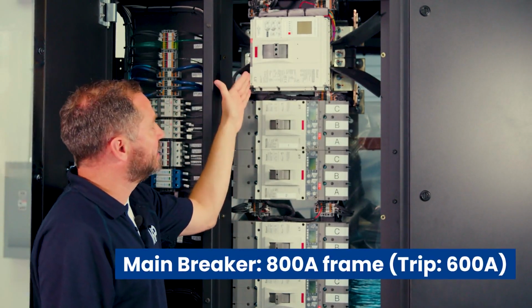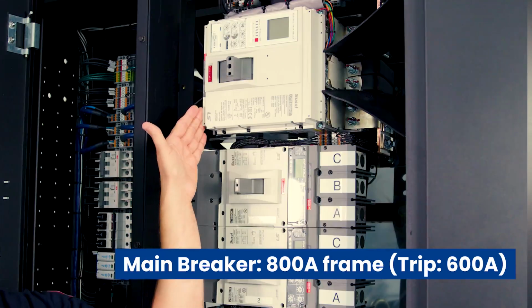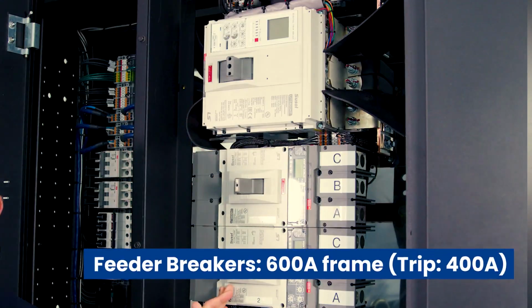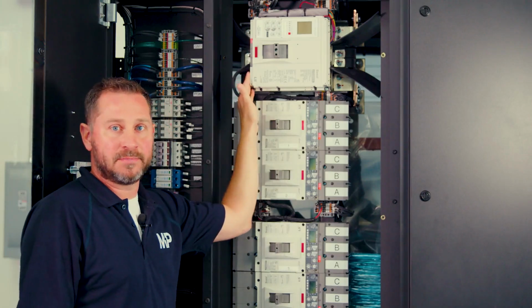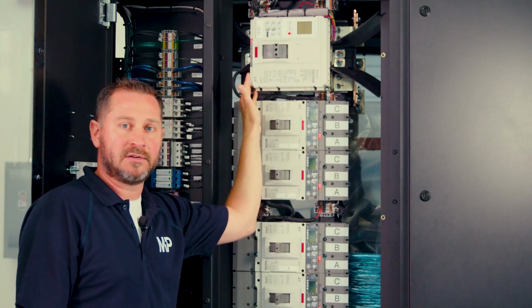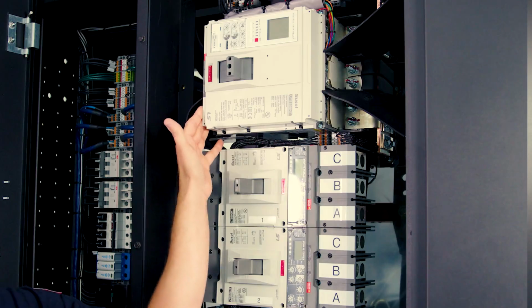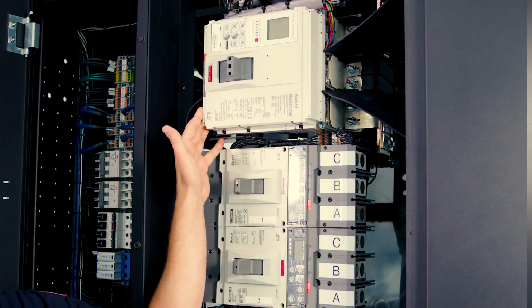Our main breaker is an 800 amp frame, but we have it tripped at 600. Our feeder breakers are going to be 600 amp frame set at 400 amp trip. These all have open, close, and trip, which will show up on my touch screen, our HMI. These are LSIG: long-term, short-term, instantaneous, and ground fault.